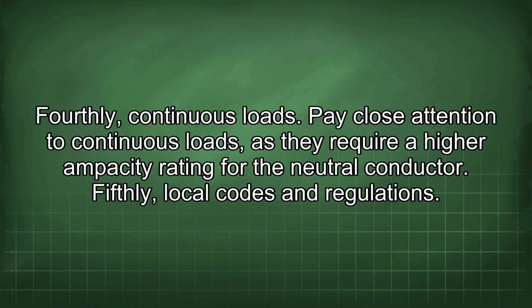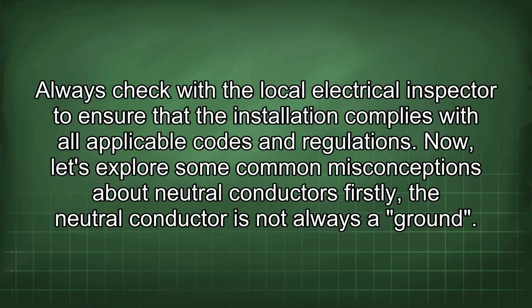Pay close attention to continuous loads, as they require a higher ampacity rating for the neutral conductor. Fifthly, local codes and regulations. Always check with the local electrical inspector to ensure that the installation complies with all applicable codes and regulations. Now let's explore some common misconceptions about neutral conductors.